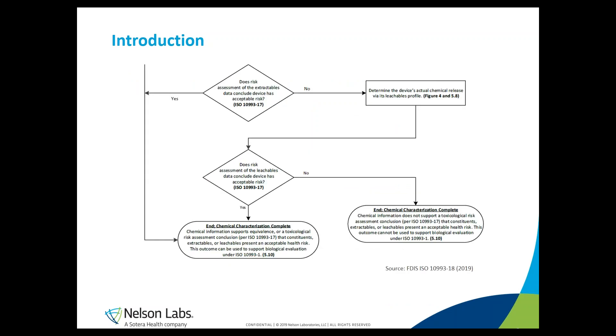At the end of extractable testing, you will need to perform a toxicological assessment. If you can demonstrate that your medical device is safe at the extractable level, then the chemical characterization is complete. If not, you will need to proceed with leachable testing. At the end of this second testing phase, you will perform another toxicological assessment. If your medical device is safe, the assessment stops there. It is important to understand that this process is not one way in, one way out — the guideline allows you to start with extractable testing if that is best for you.